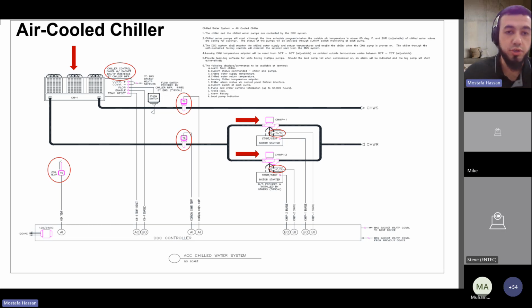Okay. There are your chilled water pumps, these two. I'm assuming they're going to be using some type of lead-lag sequence here to reduce wear and tear on one specific pump. They want the runtime of each pump to equal the other, so not one pump is working harder than the other, or maybe if the set point goes really high, both pumps would be used to supply the chilled water. Now, how do we know if the pumps have started or not? Well, do we flip a coin? Actually, we're talking about control systems here.